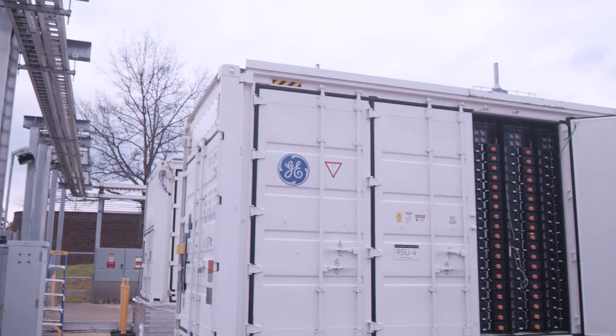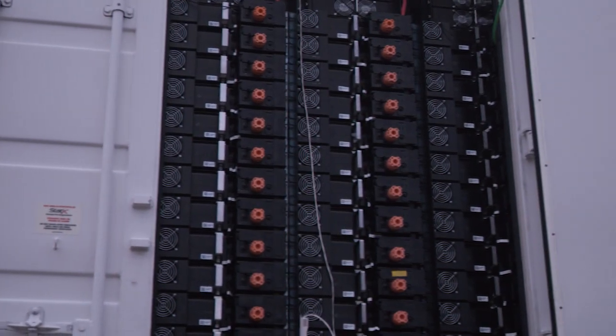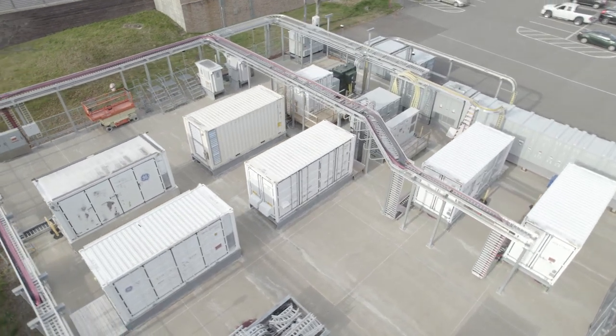Fast frequency response and grid forming are both new types of control techniques that we can apply to inverter-based resources to help ensure the stability of the power system. The idea behind grid forming is to control the inverter-based resources to provide this inherent voltage and frequency regulation that the synchronous machine-based resources, thermal power plants, gas turbines, steam turbines, have been doing for quite some time now. Fast frequency response refers to the leveraging of the inverter-based resources to arrest the frequency decline or frequency acceleration in the case of a temporary load and supply imbalance. That means that the inverter is watching the grid frequency and injecting some stabilizing active power to help prop up the grid frequency within a short time span.